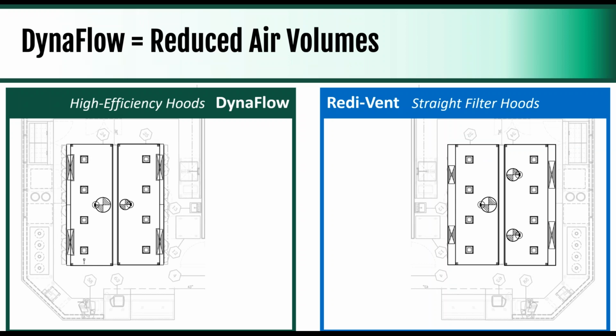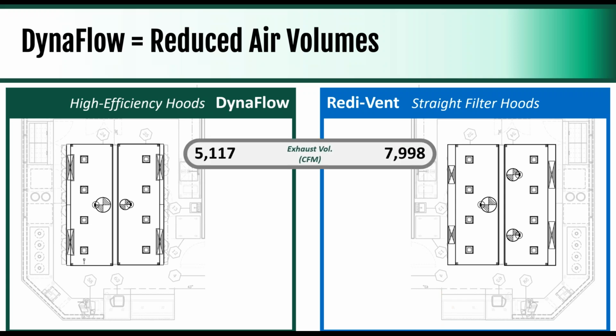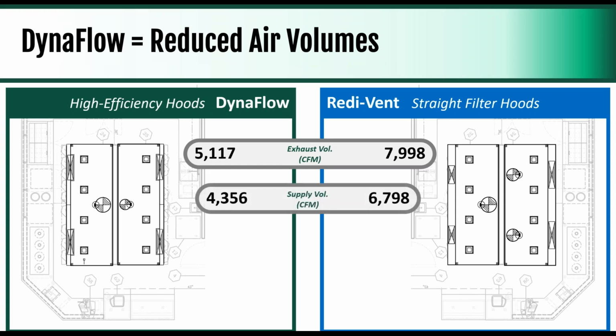So just to compare our high efficiency Dynaflow hoods compared to what we call Redi-Vent, which are straight filter hoods. So just the cheaper, you know, the cheap and cheerful, as cheap as you can get them kind of hoods. When we look at this same project, designed 2 ways, you'll see the exhaust volume drops from almost 8,000 to just over 5,000 CFM, so we've got a significant reduction there.